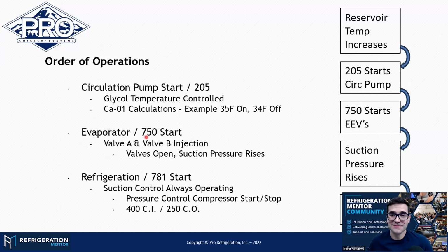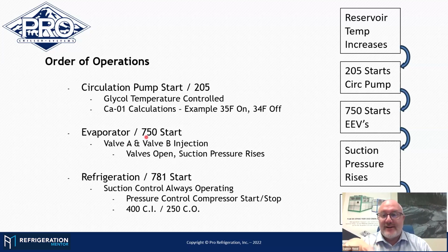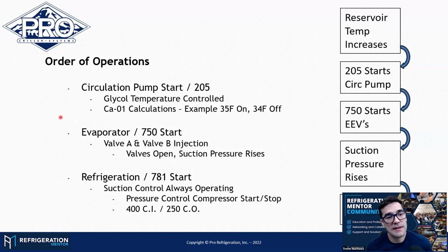Yeah. Although we're talking about and geared towards transcritical CO2 chillers, these are all things we troubleshoot on refrigeration systems all the time, whether it's a synthetic refrigerant or transcritical CO2. It's still just troubleshooting pressure controls and order of operations, all in the same way. And I just had a conversation with someone about diving into CO2, with people from all over the world, and there's a big fear of CO2, but CO2 is just refrigeration. You understand the safety side of it. We even went through a little bit already how you build your equipment. There are so many safety parameters in there, safety valves and pressure relief valves. Even if something does happen, there's protection.